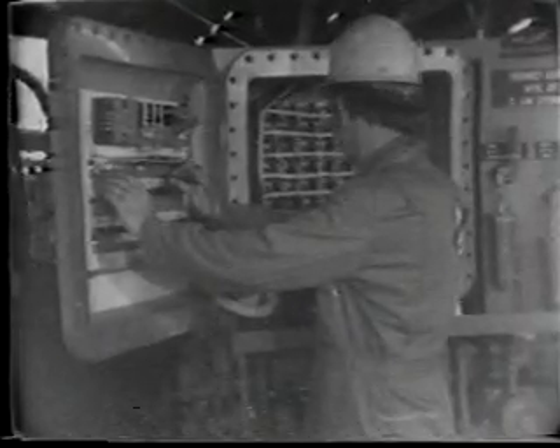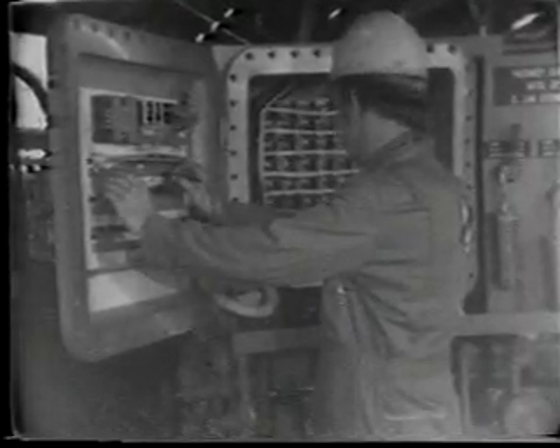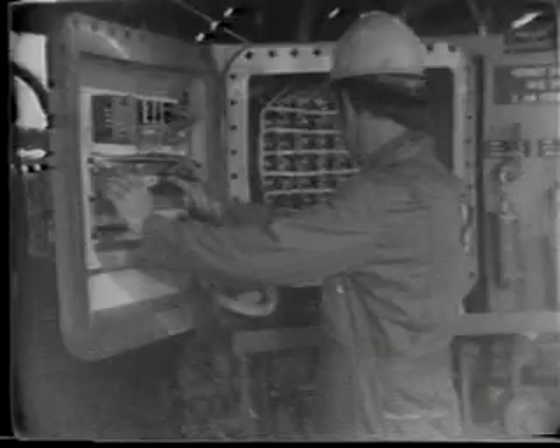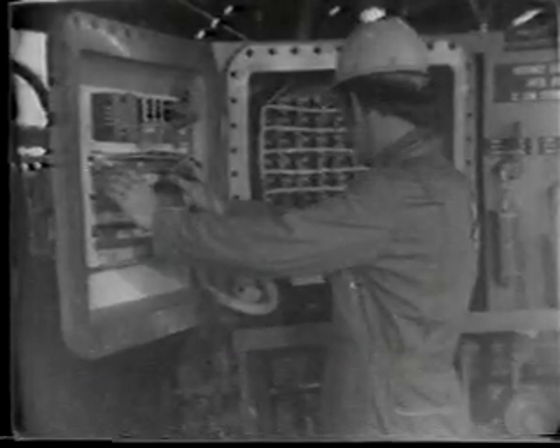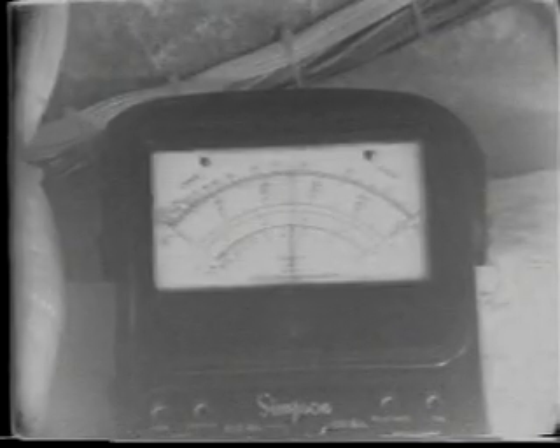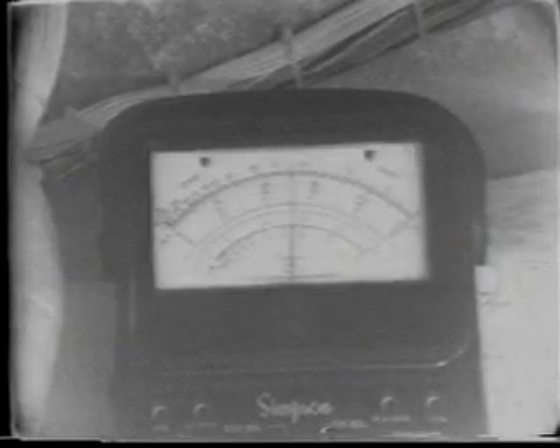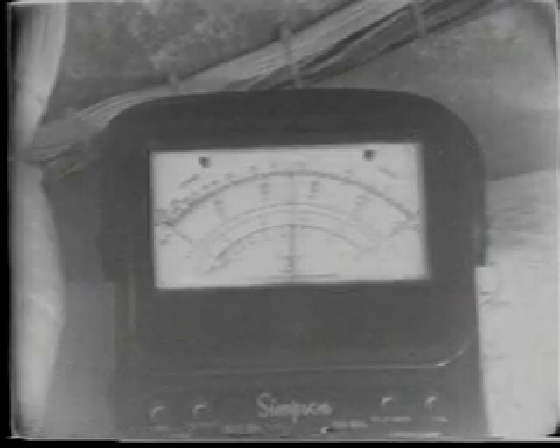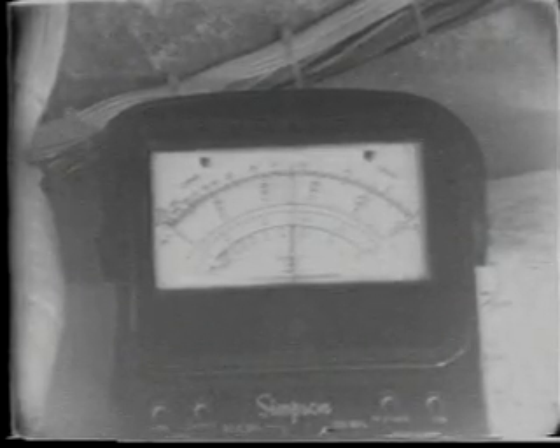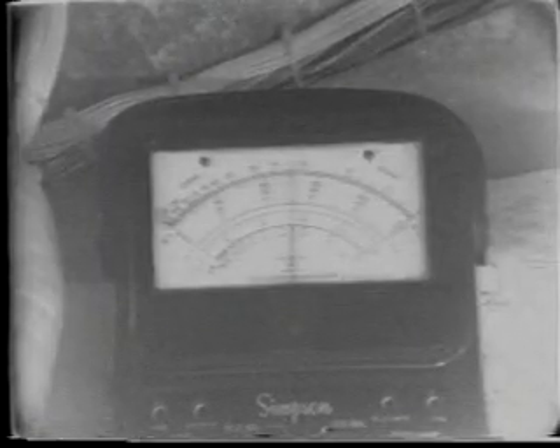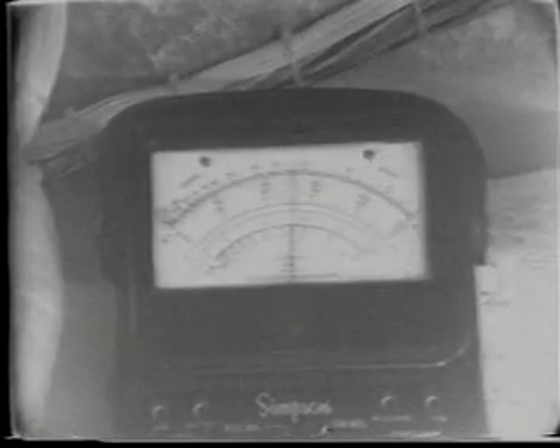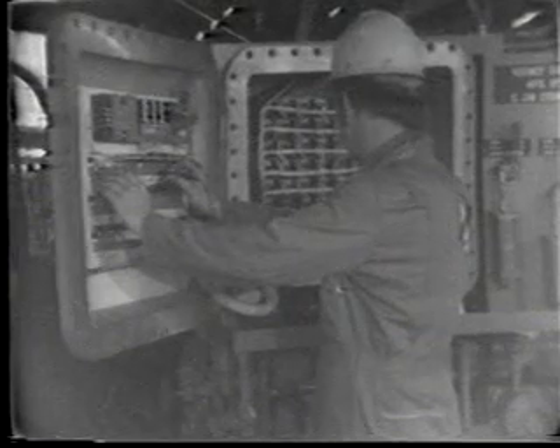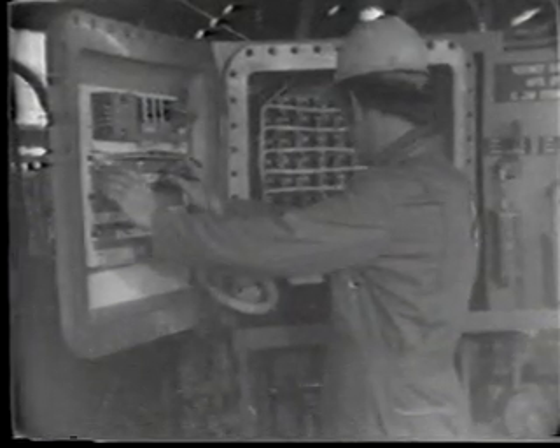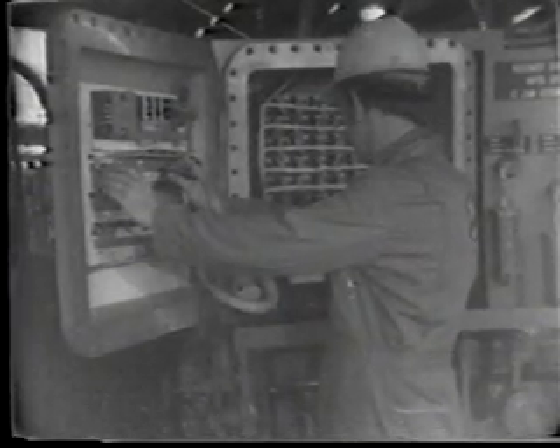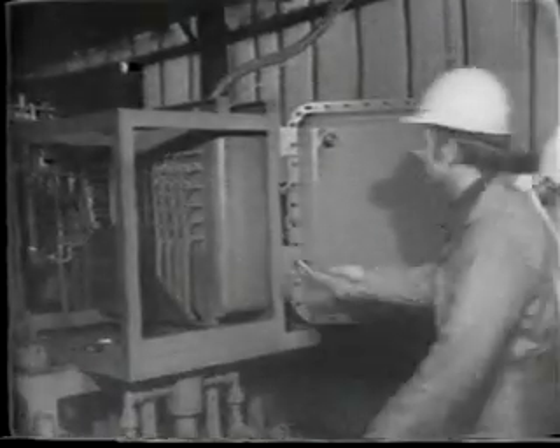If voltage is not present at the lamp socket in the panel, then use the schematic and check for voltage across the terminals in the remote panel and then the junction box on the hydraulic control manifold. If voltage is present across the terminals at the manifold, then the problem is somewhere in the interconnect between the manifold and the lamp socket. This can be found by working your way through the interconnect until you find the short.